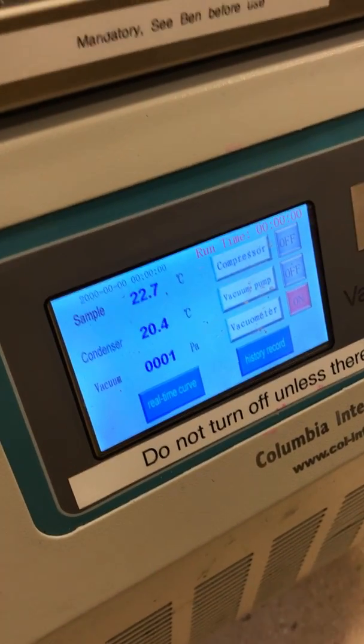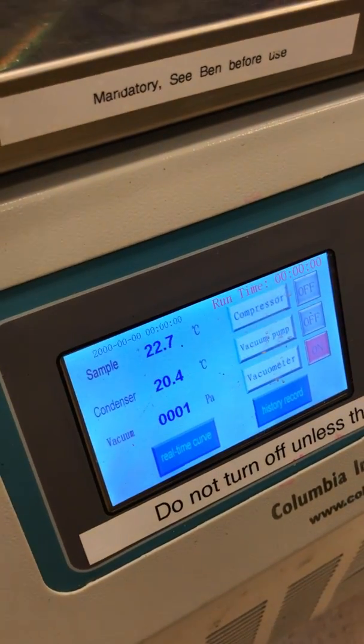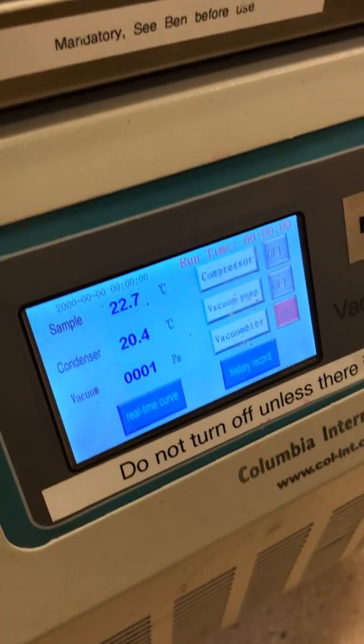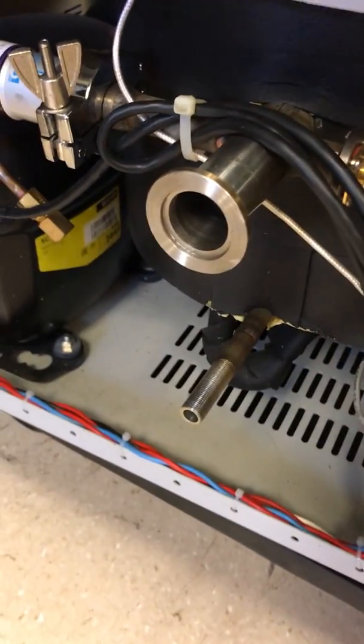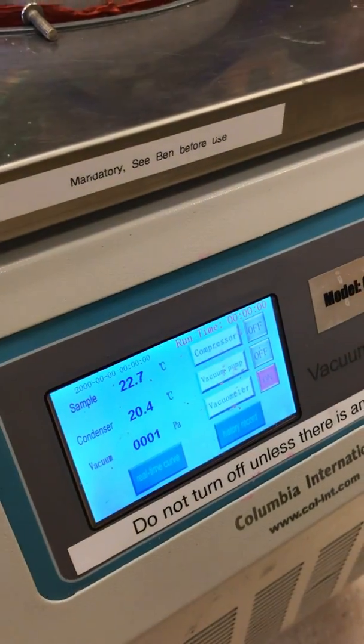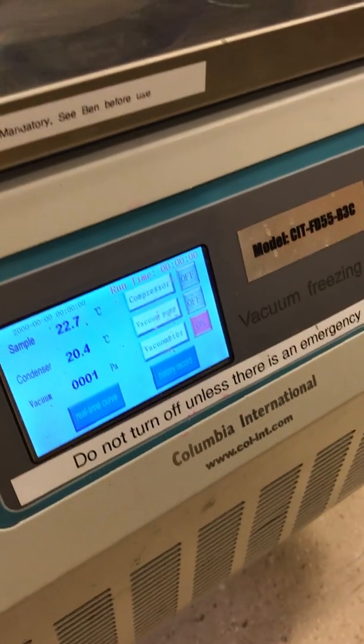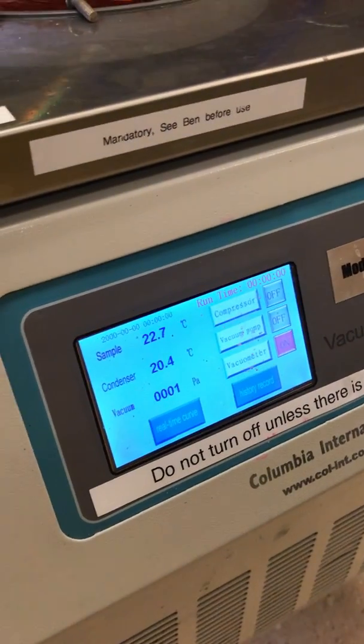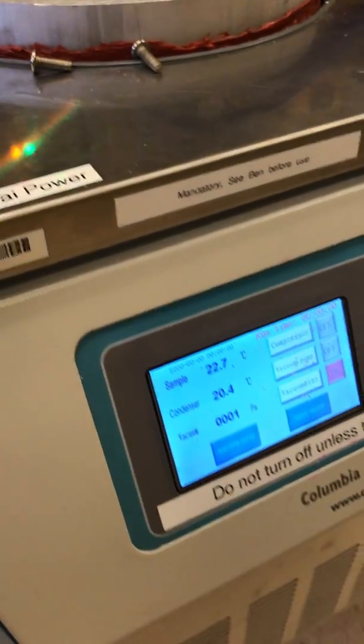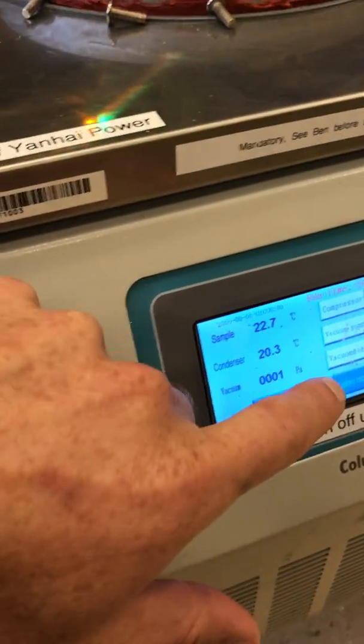So anytime I power on the unit, it tells me the system's at 1 pascal absolute. I know that's not the case because right now the system is open to ambient. It should be reading somewhere in the tens of thousands up to 100,000 pascals, and that's obviously not what's being seen right now.